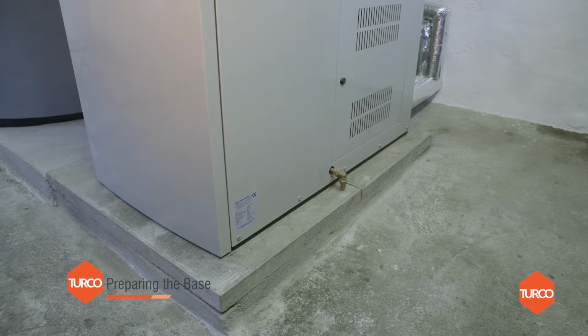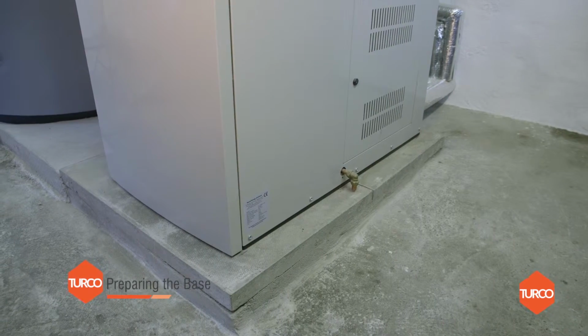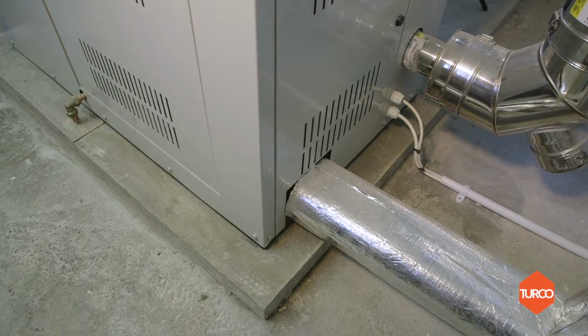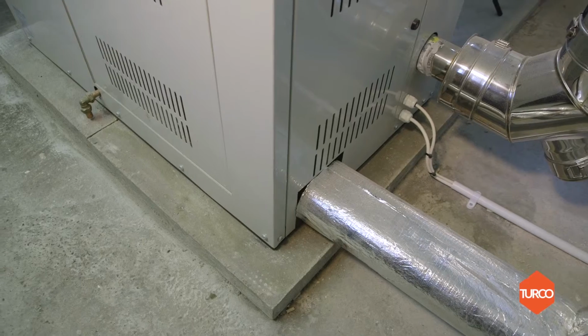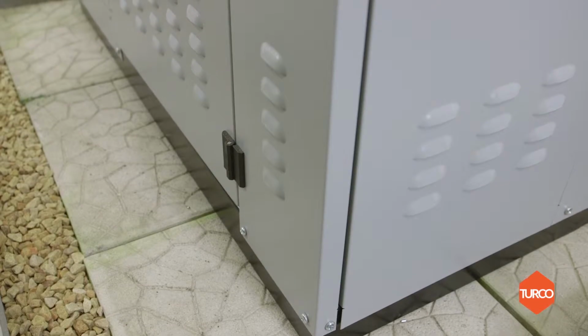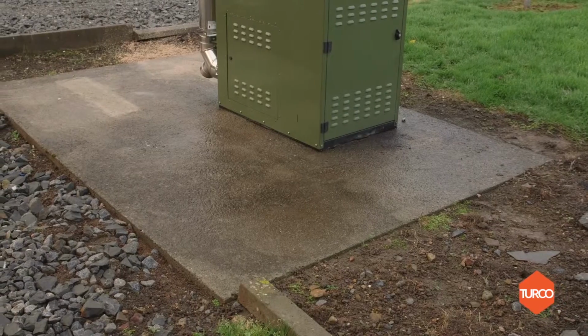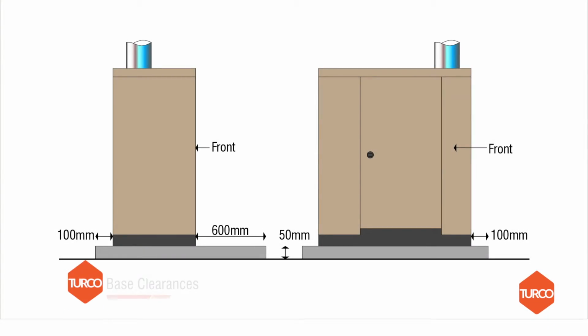Preparing the base. For internal boilers, there is already likely to be a non-combustible concrete or tiled base in the plant room where the unit is to be placed. For external boilers, it may be necessary to install a base. The base needs to be 50 mm high and should project a minimum of 100 mm beyond the sides and the rear of the boiler and at least 600 mm to the front.